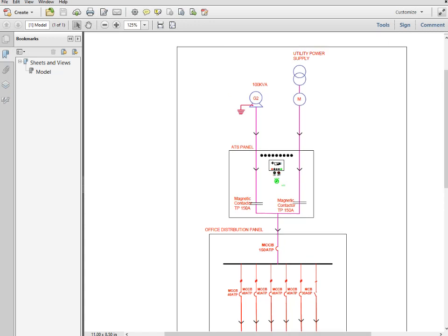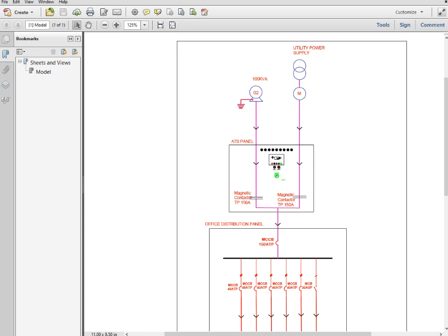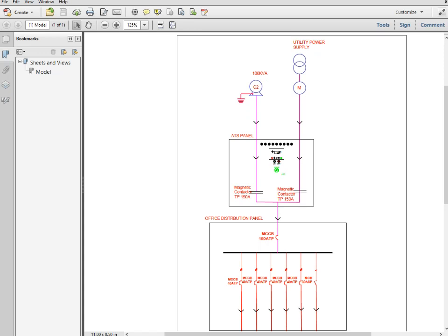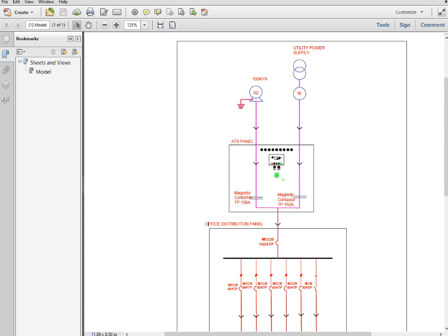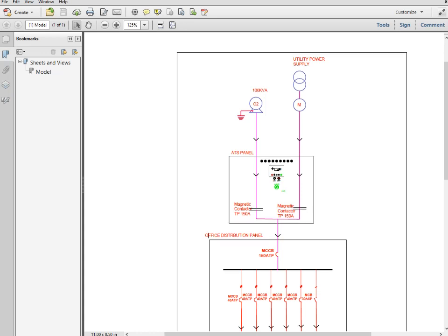As you can see in this figure, at the top is a utility transformer, and this is the energy meter which is placed outside of your house. The power travels from the utility power supply to the energy meter of your home, and then it goes to a panel called the ATS panel. If you are not using a generator as backup power supply, the meter supply will directly go to your home DB — the distribution panel, also called the home DB. The first supply is the utility power supply provided by your local supplier or government organization, and the second is backup power supply used in case of failure of the main power supply.